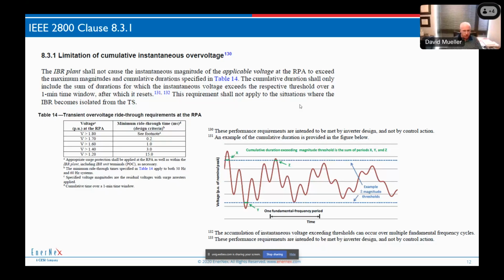The other requirement, for cumulative overvoltage, comes from the graph, which shows an example of how this is calculated over time. This is basically trying to replicate what's going to happen in a surge arrester as far as energy, and to ensure that arresters don't have a problem with these overvoltages. This same chart came from 1547, and in the recent revisions to 1547, a lot of effort was put into explaining this graph much better. I think that'll be a big improvement when 1547 does get published, which I expect will be about a year from now.